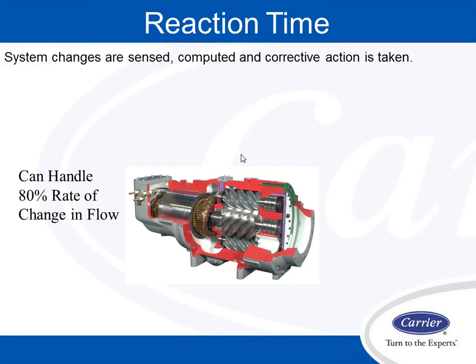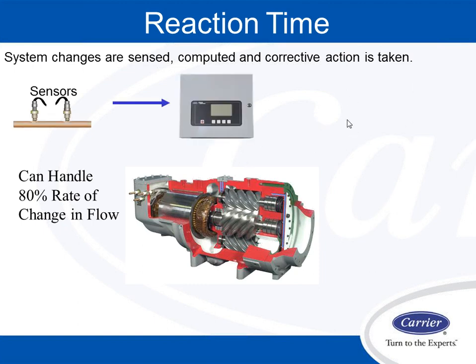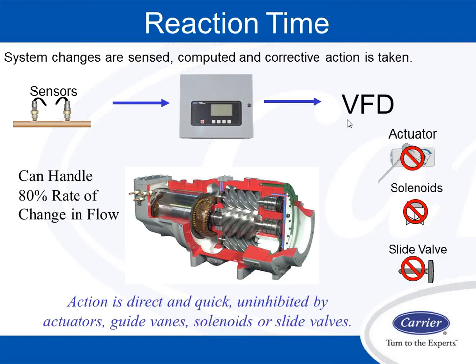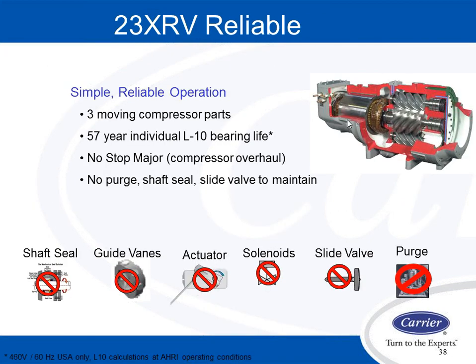Okay, so the reason why it can react so fast is because we have sensors. It goes to our control panel, which then adjusts the VFD. I have no actuators, solenoid valves, or slide valves. The machine can also handle 80% rate of change in flow, which is really important. So variable primary flow with this chiller is absolutely fantastic.